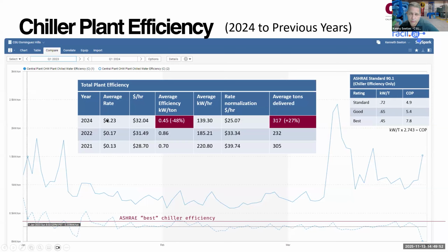In 2024, this is our efficiency at the bottom, right? This efficiency level is the total plant though. I don't really worry about the actual chiller efficiency, because it's about the total cost of making chilled water. You can see that ASHRAE is telling us that at the chiller, our best is 0.45, and we were averaging about 0.45. Before that, we were 0.86, 0.7. We came up with these numbers by taking a year's worth of 15-minute trend data, throwing out the high, throwing out the low, and comparing them together.